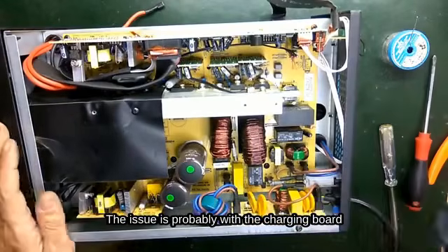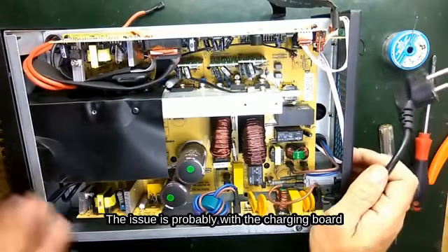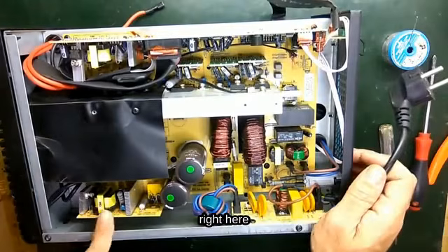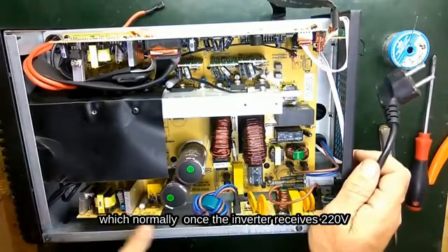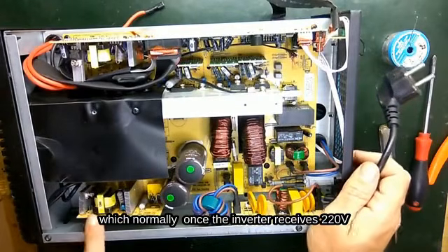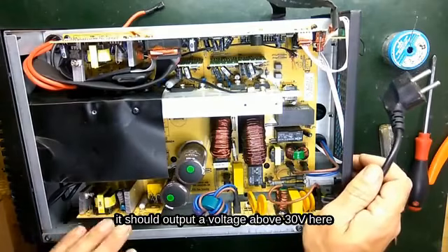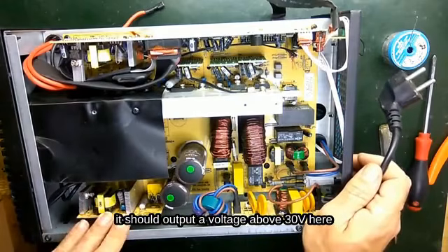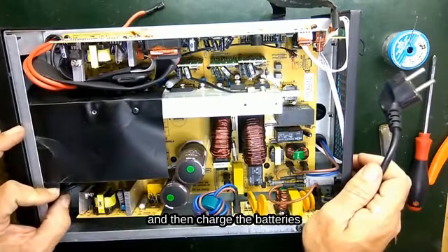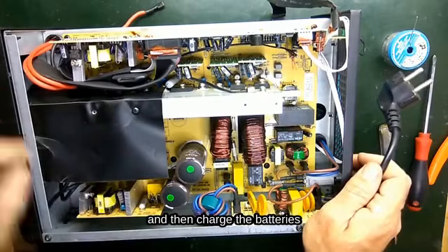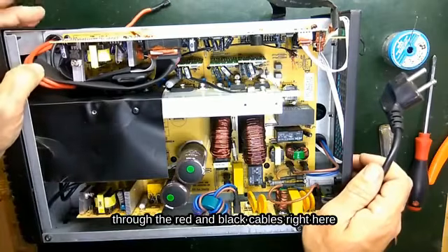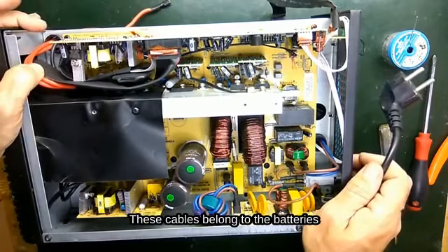The issue is probably with the charging board right here, which normally, once the inverter receives 220V, should output a voltage above 30V here, and then charge the batteries through the red and black cables. These cables belong to the batteries.